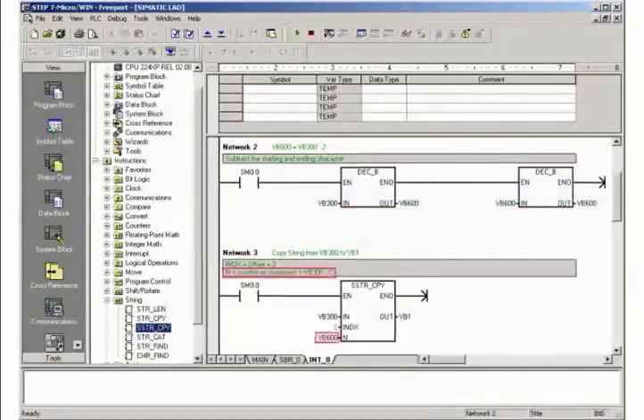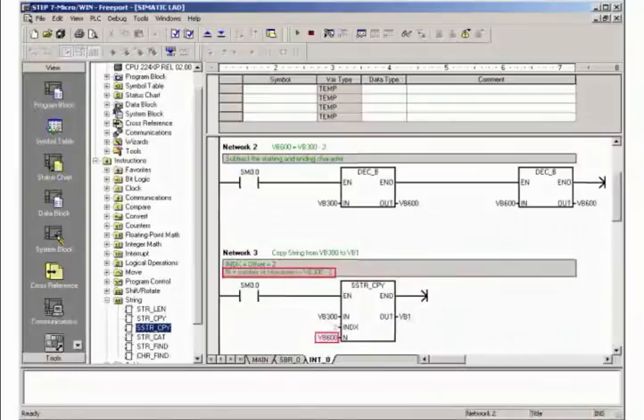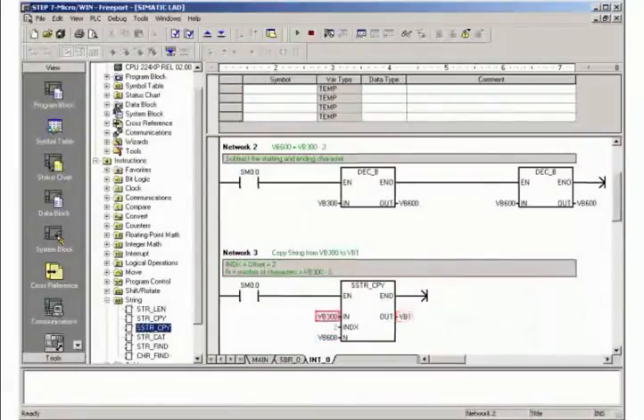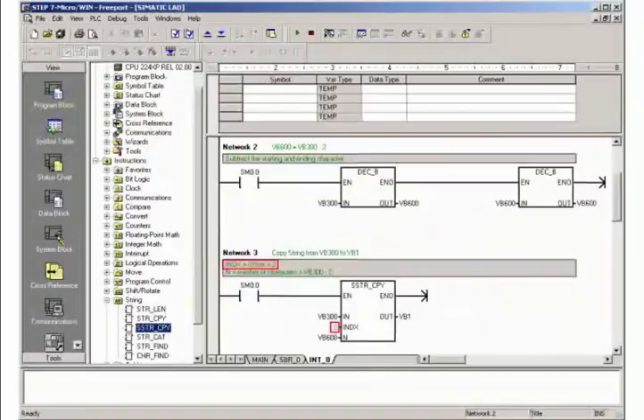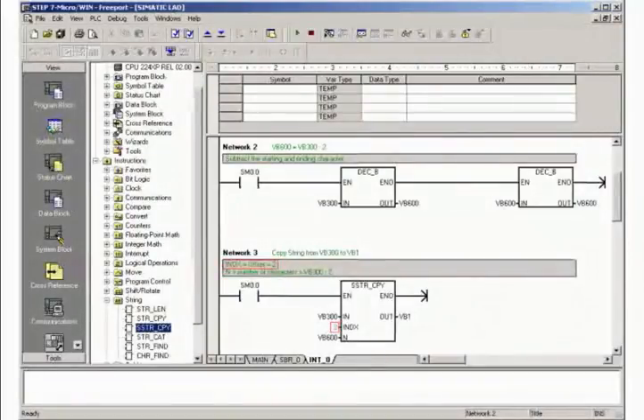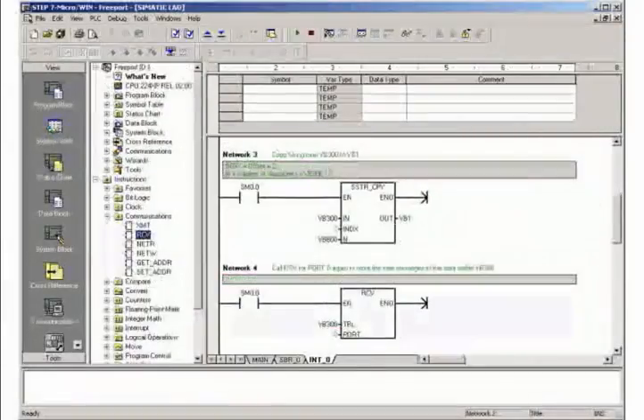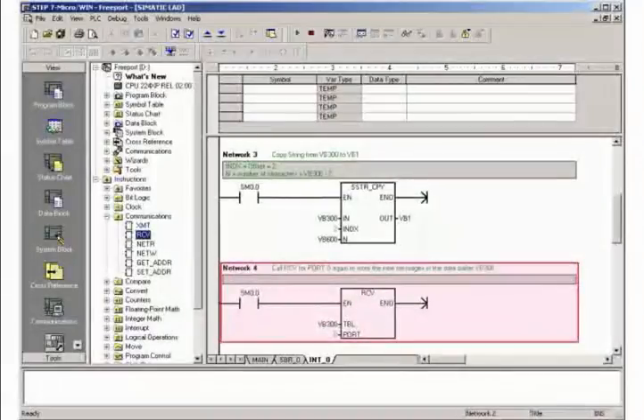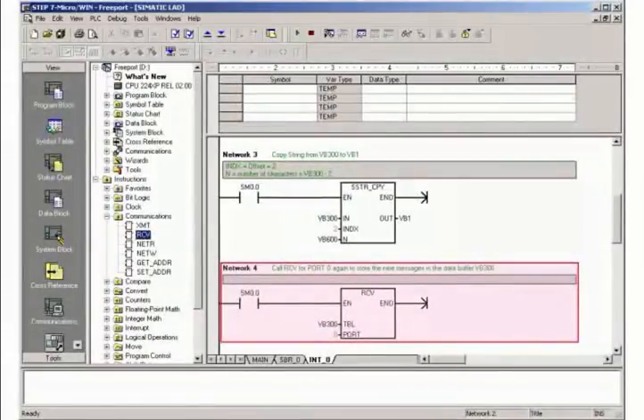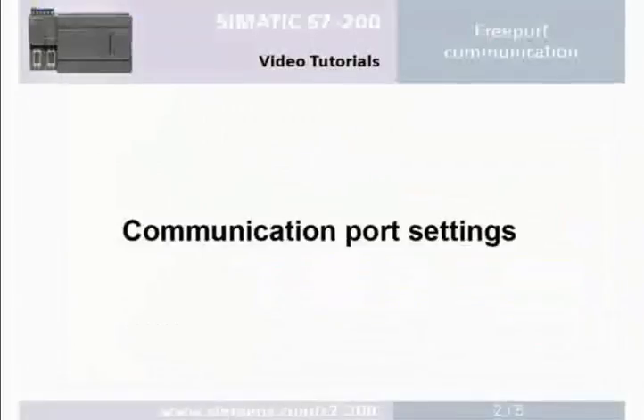In Network 3 the number of characters of the received user data is copied to the desired target address from the start address of the data buffer plus an offset of 2, due to the number of characters as well as the start detection character. In Network 4 the communication block RCV must again be called in order to receive the next message. Step 2: communication port settings.